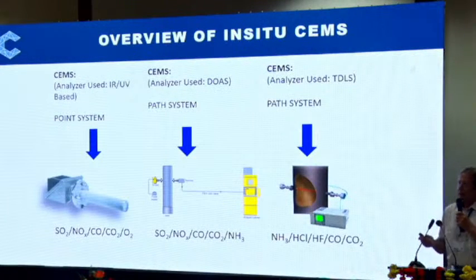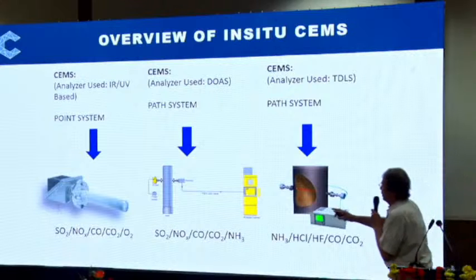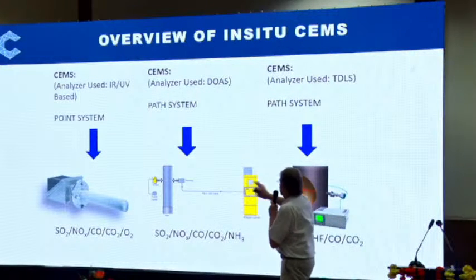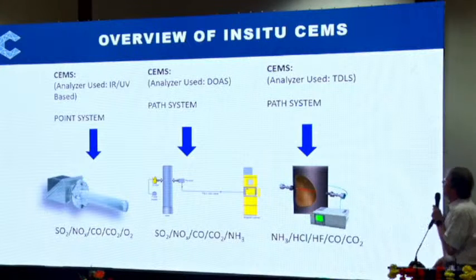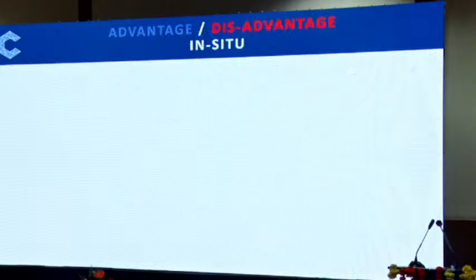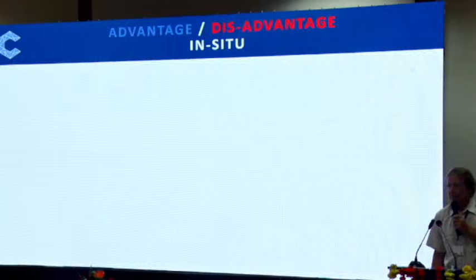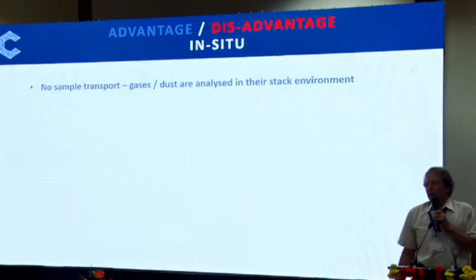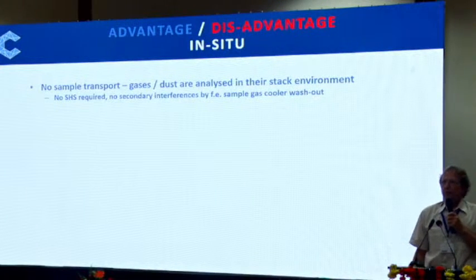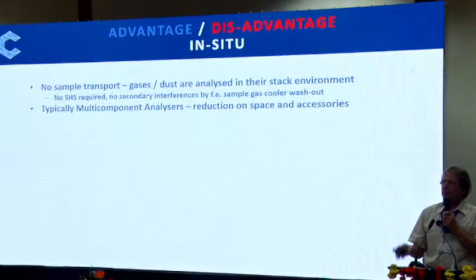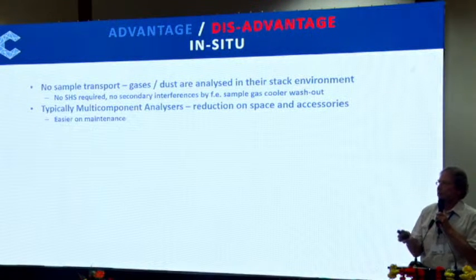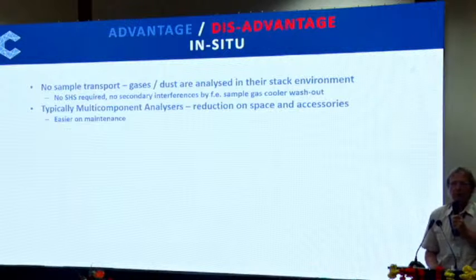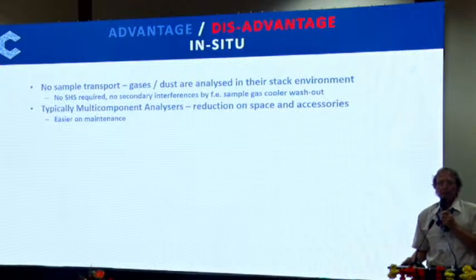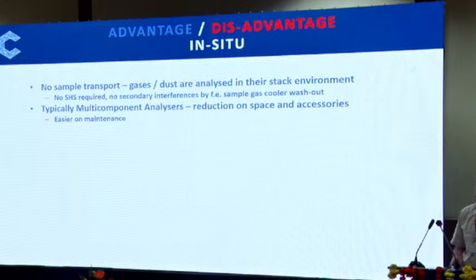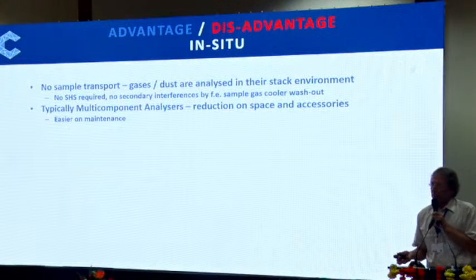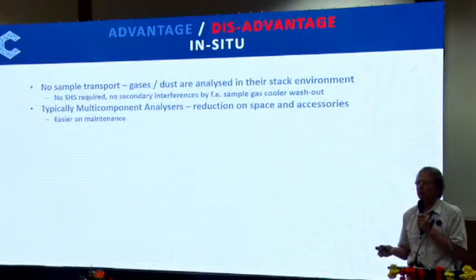Now, I have an in situ CEMS. Point measurement, cross-stack measurement. That's the path systems and point systems. Now, what are the advantages and disadvantages of that? Number one, I do not touch the sample gas. I leave it where it is. I analyze it where it is in the stack. I don't need a sample handling system. I don't have to transport the sample gas to the measurement. I do not have any loss of material.